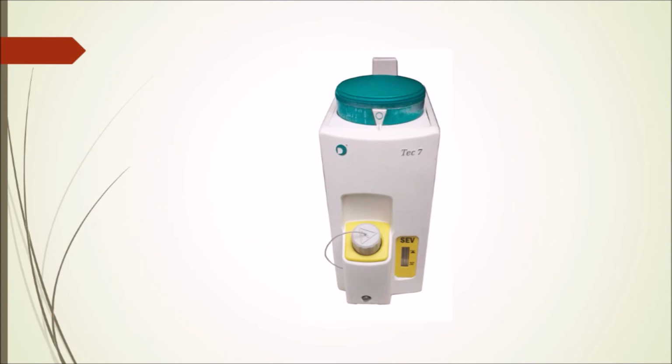On the other hand, the fresh gas sent to the vaporizing chamber becomes fully saturated with vapor. At the exit of the vaporizer, the bypass gas meets the chamber gas, and the two mix. The resulting output depends on how much fresh gas went through each pathway. Then it goes to the patient.